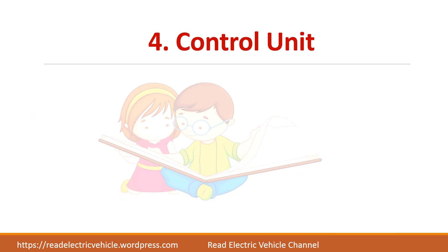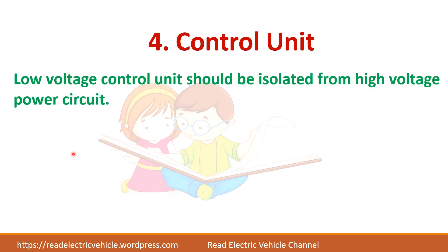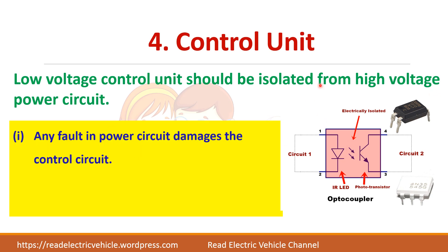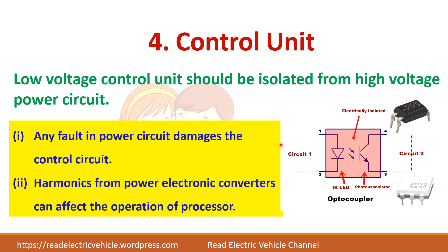An important point about the control unit: the microcontroller may operate at a low voltage of 5V or 3.3V, whereas the power circuit — the converter and DC motor — operates at a higher voltage. Both must be isolated for two reasons: first, any fault in the power circuit can easily affect the microcontroller; second, power converters are a major source of harmonics which can affect the processor. Isolation can be achieved using optocouplers or isolation transformers.